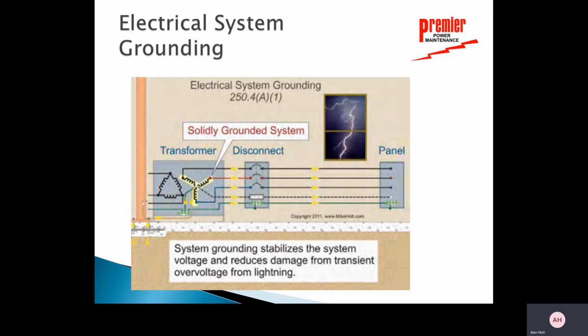So looking here, the note is that the system grounding stabilizes the system voltage, okay? Reduces the damage from transient overvoltage to equipment. So it could be a lightning strike, a line gets into something else, all those sorts of things. But here's my panel. Here's my transformer. It's solidly grounded right there. Okay, so if it comes in this way, I want the current to flow and I want it to go to this ground, okay? I've got to keep it there.